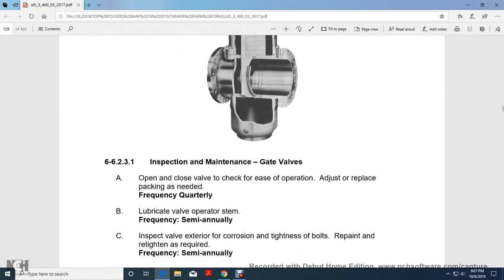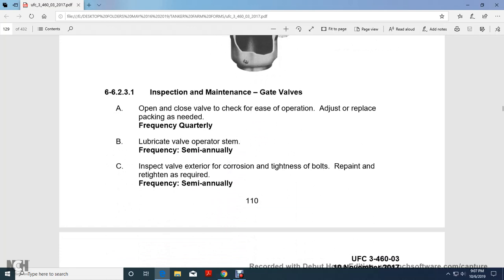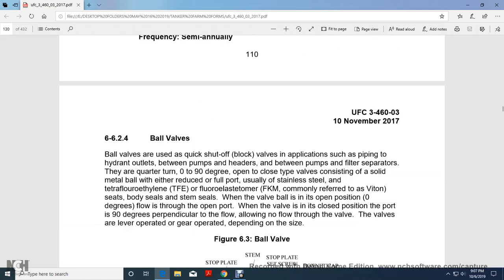Inspection and maintenance of the gate valve: open and close the valve to check for ease of operation, adjust or replace the packing as needed, quarterly. Lubricate the valve operator stems semi-annually. Inspect the valve exterior for corrosion and tightness of bolts, repaint and retighten semi-annually.